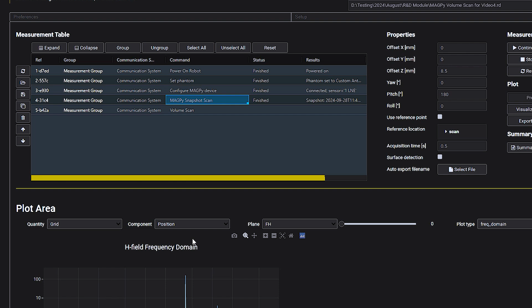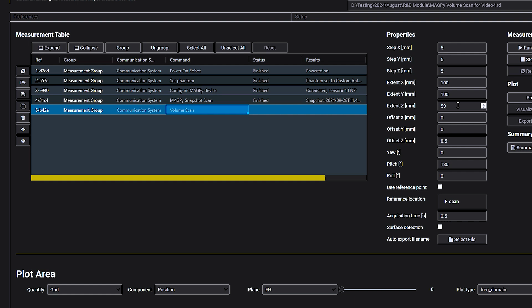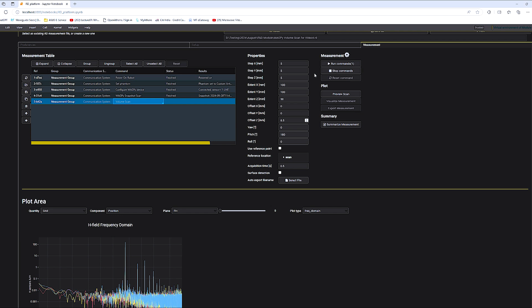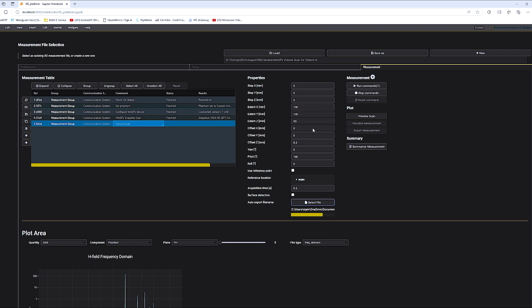Now, we will conduct a volume scan over a 100 by 100 by 50 millimeter grid with 5 millimeter resolution on XY and at 8.5 millimeter from the source. I will set the system to automatically export the measurement results to a CSV file once the scan is complete. Let us start the measurements.